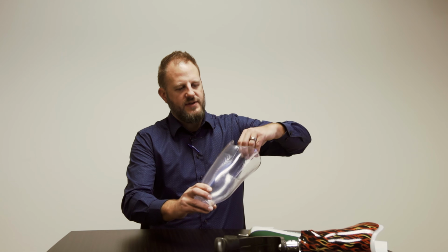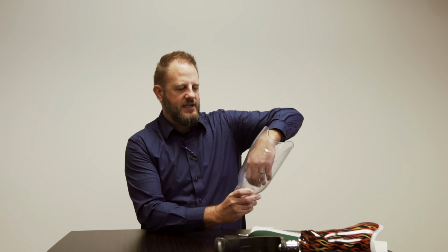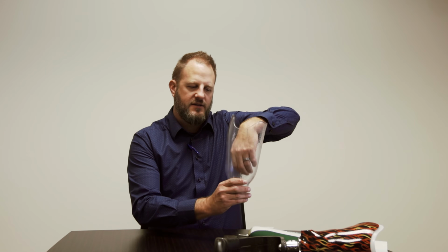And so the limb would go inside of this socket, and we can check to see that the socket's fitting correctly because we can visually see through that. And so areas of high pressure would blanch with white over the end of the limb, or areas of gapping or lack of contact, we would be able to determine that the socket needs to be changed or modified.